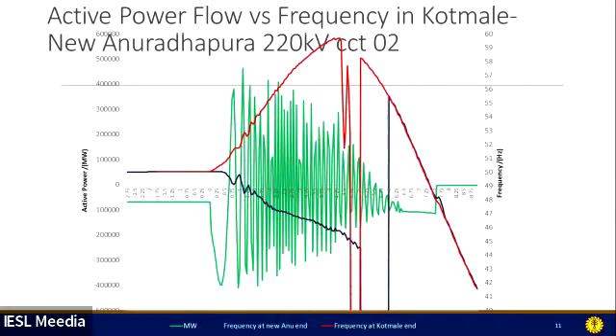So that is the graphical representation. At this time, Kotmale Biyagama circuit 2 trips, so frequency increases. The red curve shows the frequency of Kotmale. The black curve shows the frequency of Anuradhapura or the rest of the grid. This is the active power fluctuation that occurred in the Kotmale Anuradhapura circuit. After that, the main system collapsed.